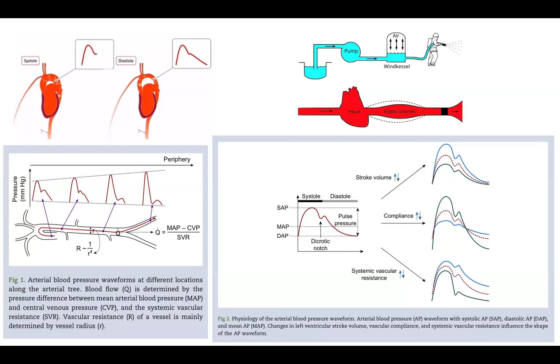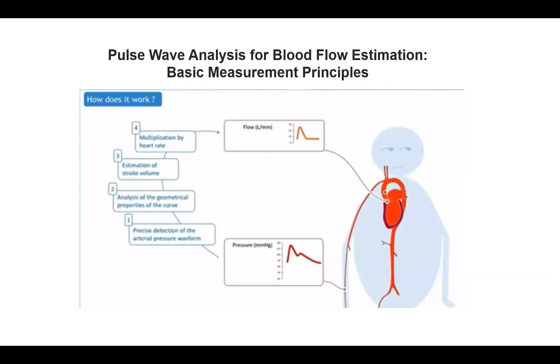So this is how it works. Pulse contour analysis is performed by precise detection of the arterial pressure waveform, specifically detecting the dicrotic notch, and performs a geometric analysis of the curve to estimate the stroke volume. For the geometric analysis of the arterial pressure waveform to estimate stroke volume, different models use different algorithms, like the 2-element Windkessel model, 3-element Windkessel model, Modelflow and HEMS techniques, long-time interval analysis, pulse power analysis, pressure recording analytical method, etc.